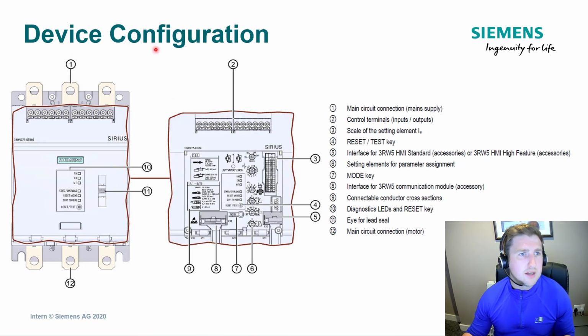So in device configuration, you can see here there's a couple of different things which you can have a look at here. You've got number 1 and number 2, so that's the main supply going in. Number 12 is the main supply which is going to be feeding the motor. Number 10 here indicates that you've got diagnostics and LEDs and also a test and a reset key. Number 11 here is the lead seal for the unit. Number 2 here, as you can see, these are the connections for the control circuit, which we're going to have a little bit more of a look at in a little bit more detail.